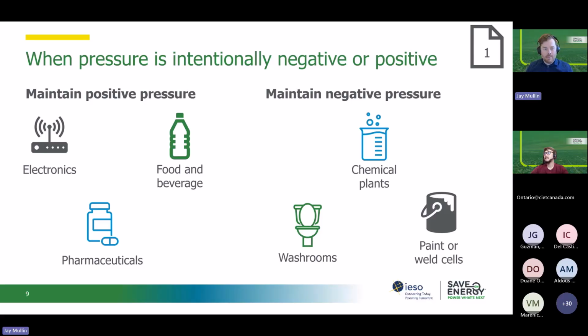And sometimes maintaining that positive or negative pressure is intentional. There are situations where you want to keep contaminants out, like if you're manufacturing sensitive electronics or food and beverage or pharmaceuticals, and it's important to maintain a positive pressure because that's pushing air out. It's going to keep contaminants out of the clean areas where you don't want them. But there are other situations where you're dealing with odors, harmful chemicals, toxic fumes, and in those, it's important to maintain a negative pressure so that those harmful chemicals or fumes don't leak into areas where they're not supposed to. So you want that negative pressure to be drawing the air in, preventing it from escaping into places where you don't want it. It should be noted that this differential, even in the intentional situations where you're purposely using it for these reasons, doesn't need to be huge.